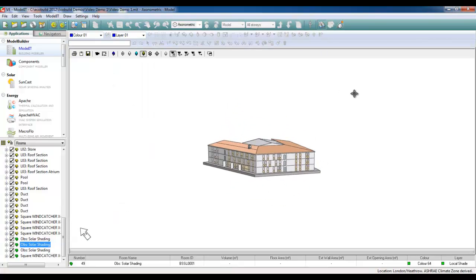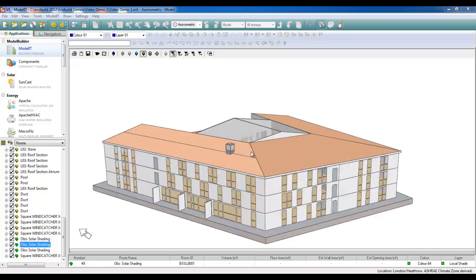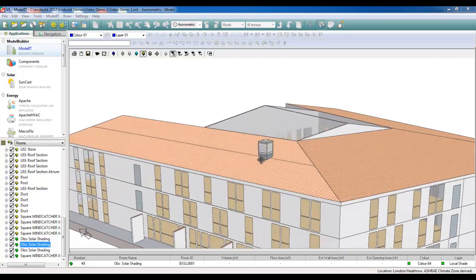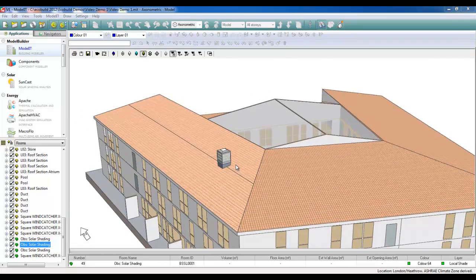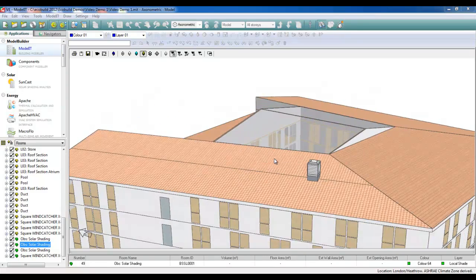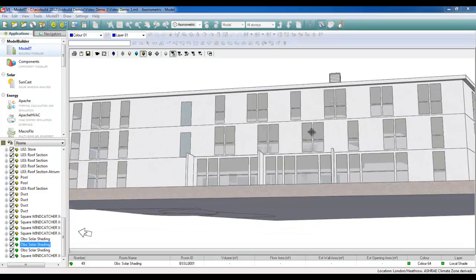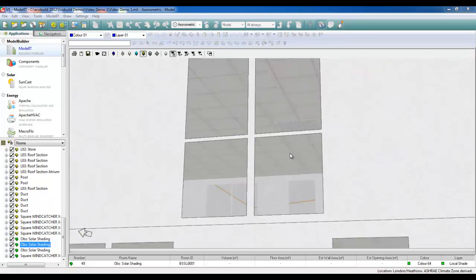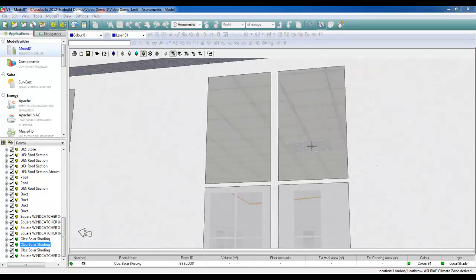This comes complete with all the constructions, the thermal templates, the MacroFlo opening profiles, and the textures. So, in terms of everything that needs to be done to that Windcatcher with regards to an Apache Dynamic Thermal Simulation, it is ready to simulate, and we can see that the damper or egg crate grill arrangement is sitting flush with the ceiling underneath.